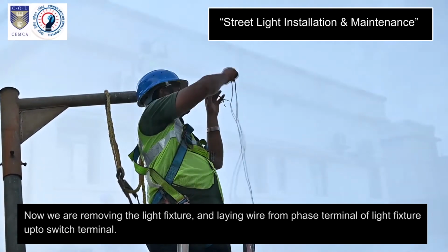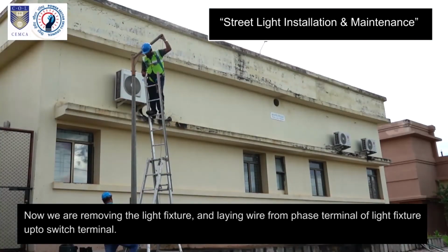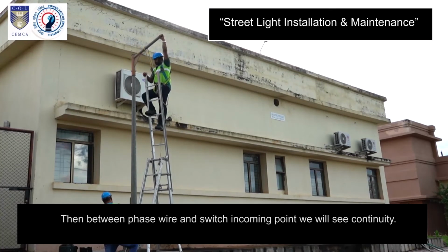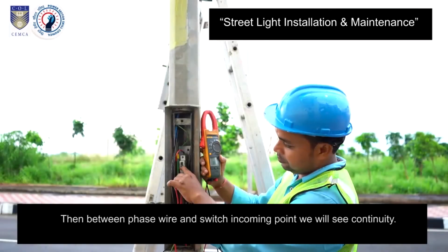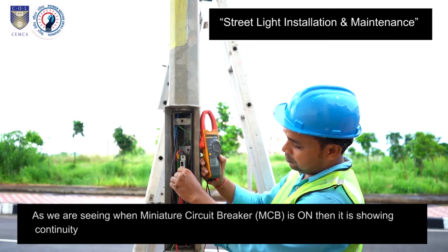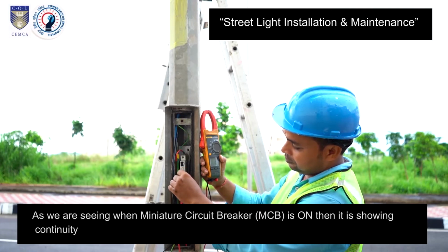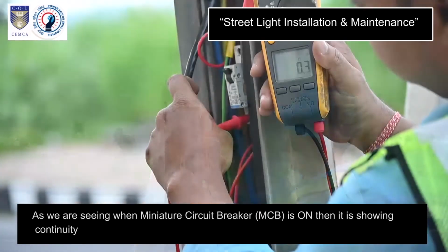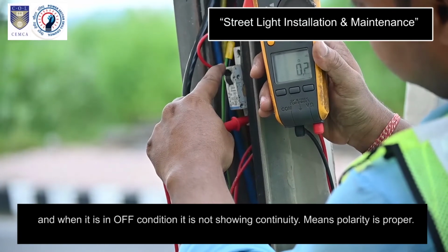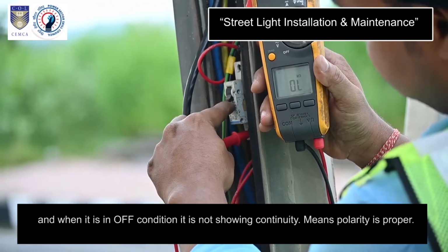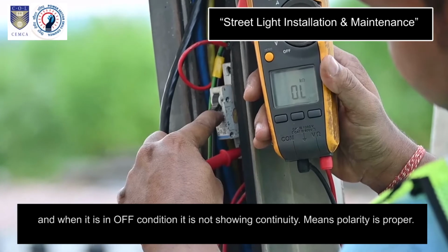Now we are removing the light fixture and laying wire from the phase terminal of the light fixture up to the switch terminal. Then between the phase wire and the switch incoming point, we will see continuity. As we are seeing, when the miniature circuit breaker MCB is on, it is showing continuity, and when it is in off condition, it is not showing continuity. Means polarity is proper.